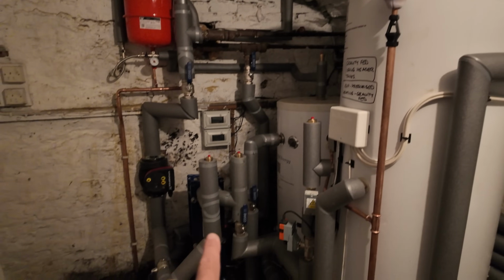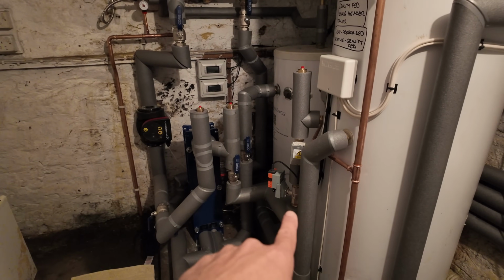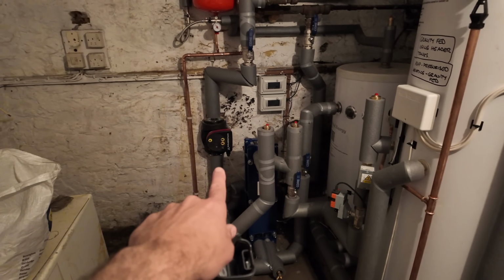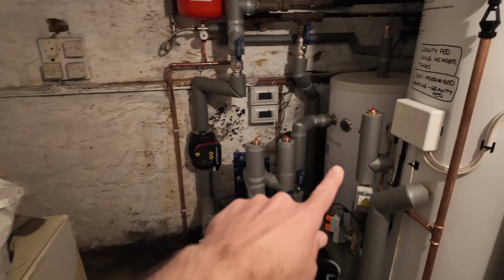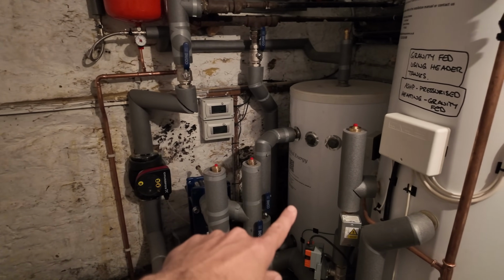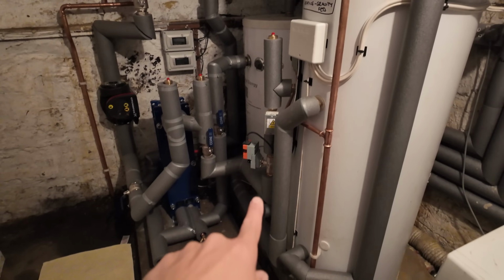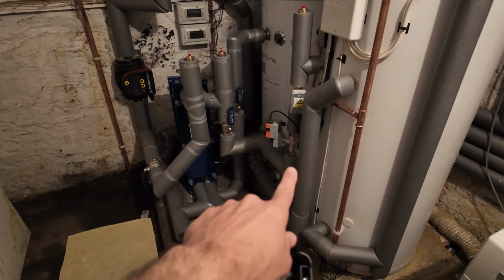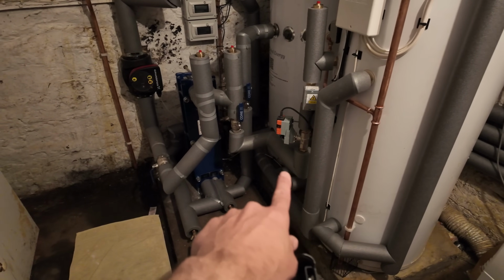We have got the heat exchanger. We've got a big Belimo valve there. That is the distribution pump. That thing in the corner is a volumizer, not a buffer tank. So we've piped direct. So we've piped direct to that Belimo valve there.